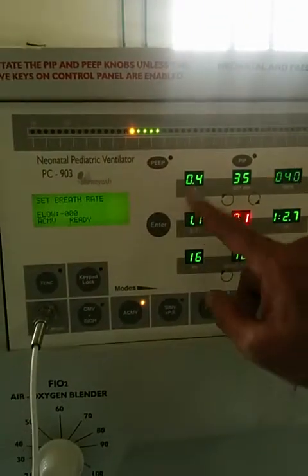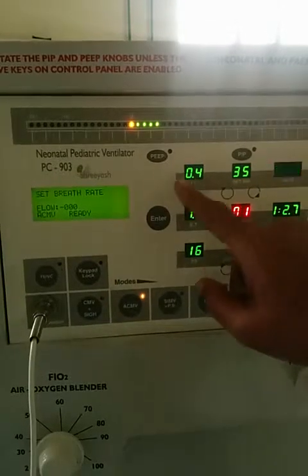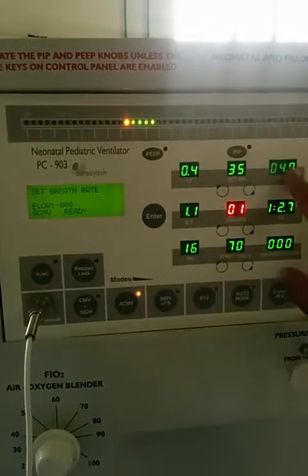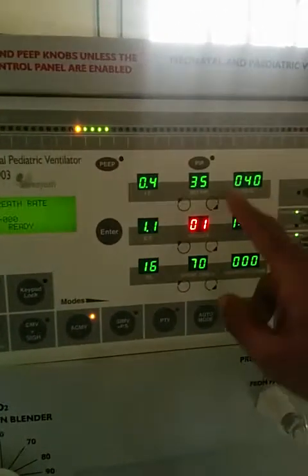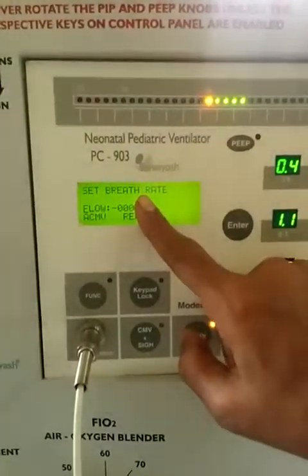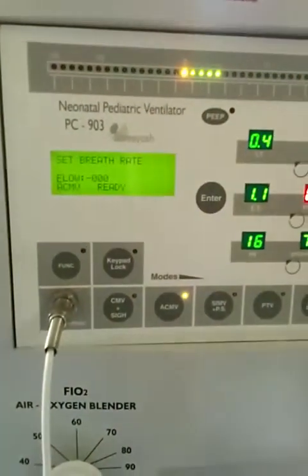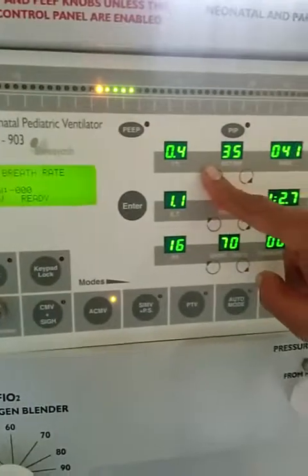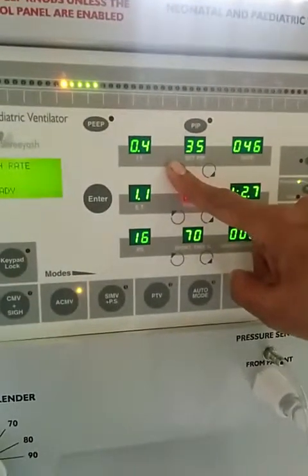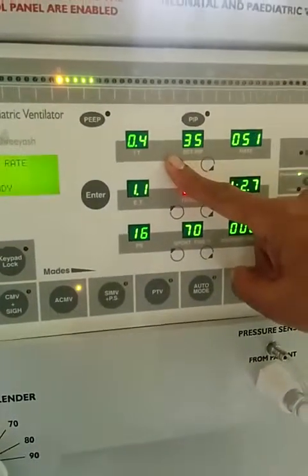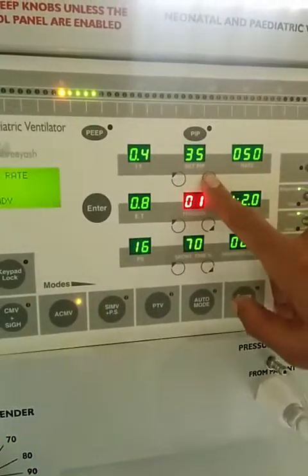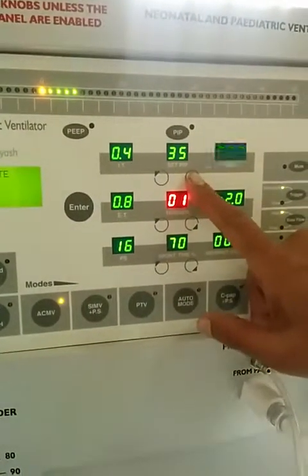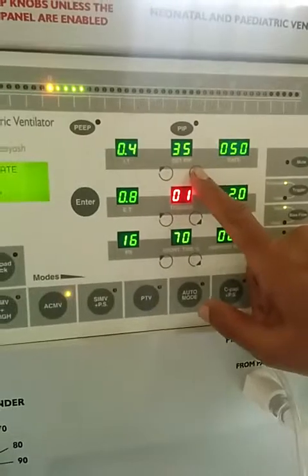Once I acknowledge the inspiration time, the display will go to the rate setting, and simultaneously the LCD will indicate set the breath rate. Now again, by using these up and down keys, you can set the breaths per minute or respiratory rate, whatever you call it.